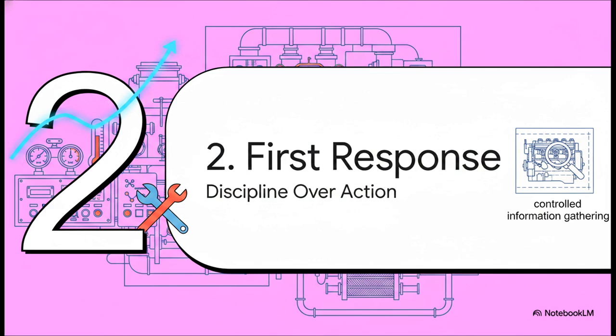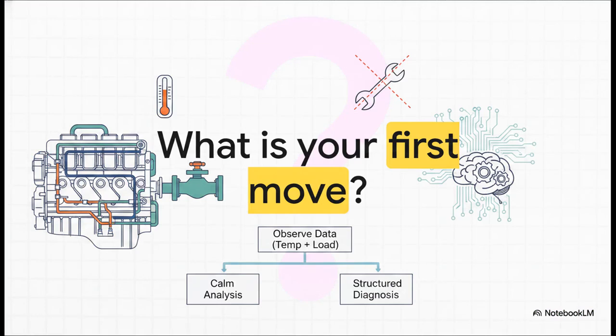So you see that temperature start to climb. Your first response has to be disciplined. This isn't the time to start randomly twisting valves or switching over pumps just to see what happens. Your first job is to gather information in a controlled way. Rushing in and changing things almost always makes the diagnosis harder. So, picture this. You're on watch. The jacket water temperature is, say, 3, maybe 5 degrees higher than it should be for the current load.